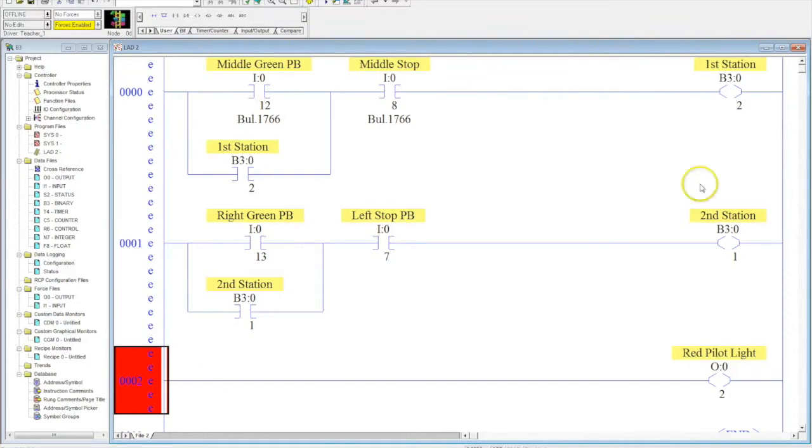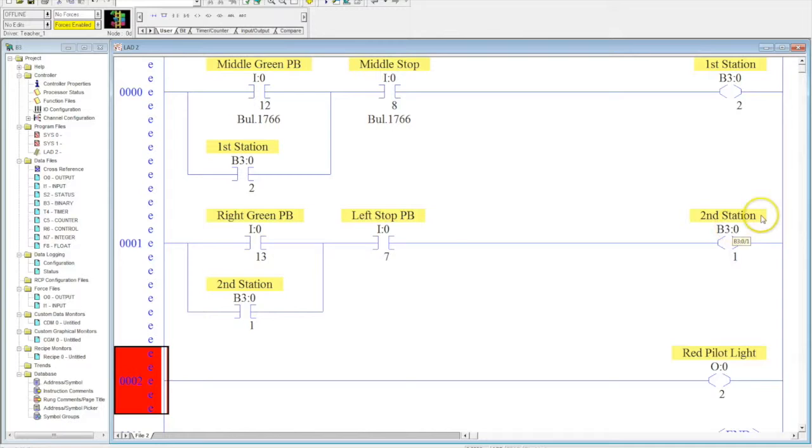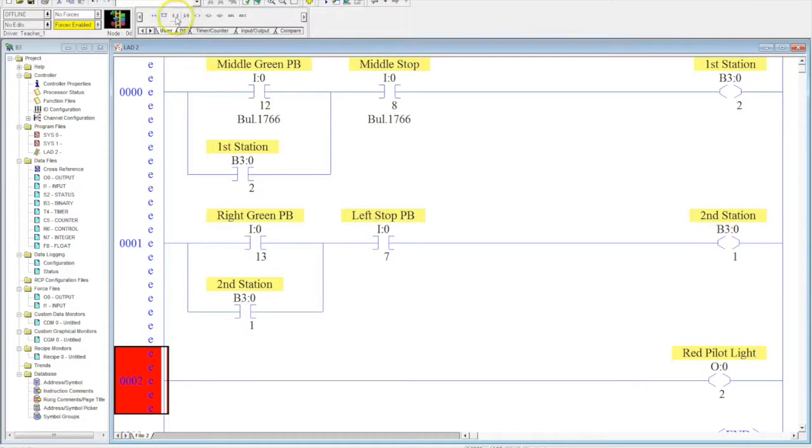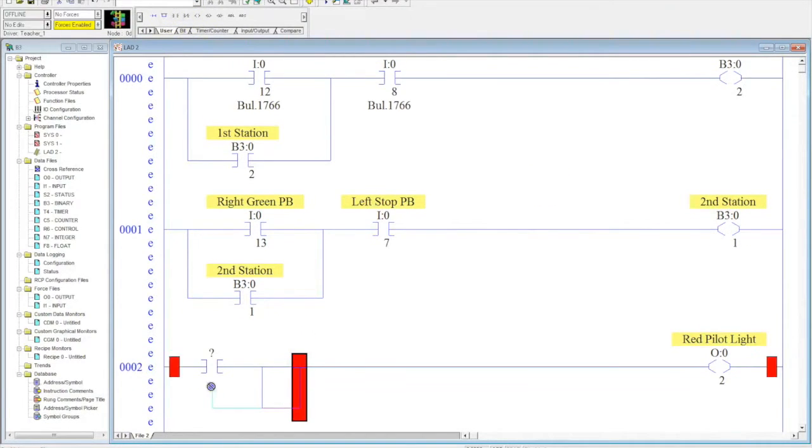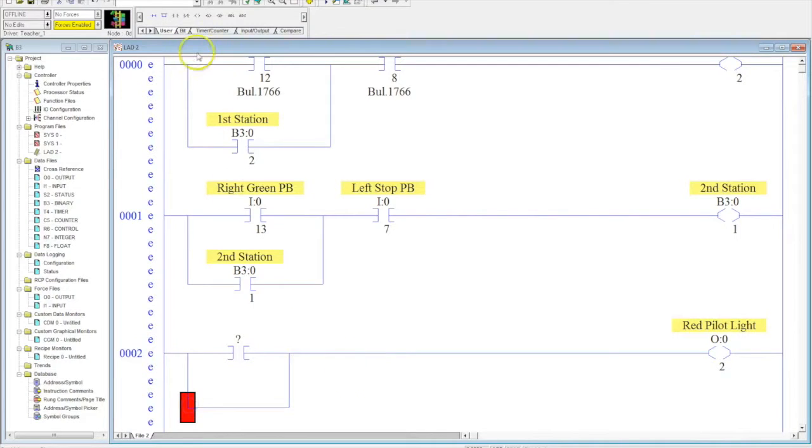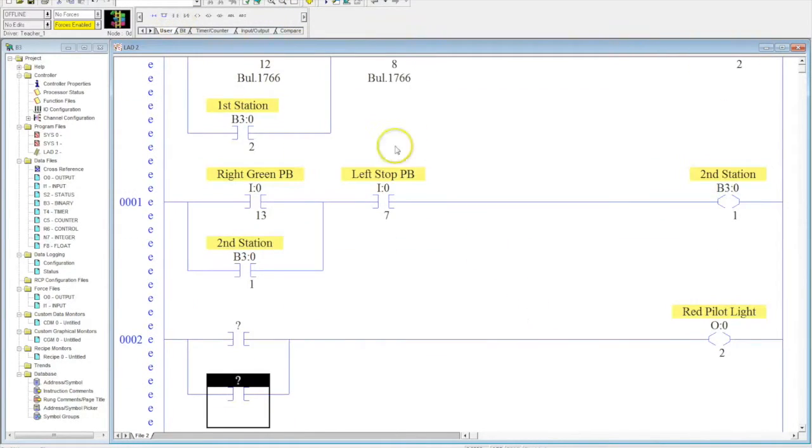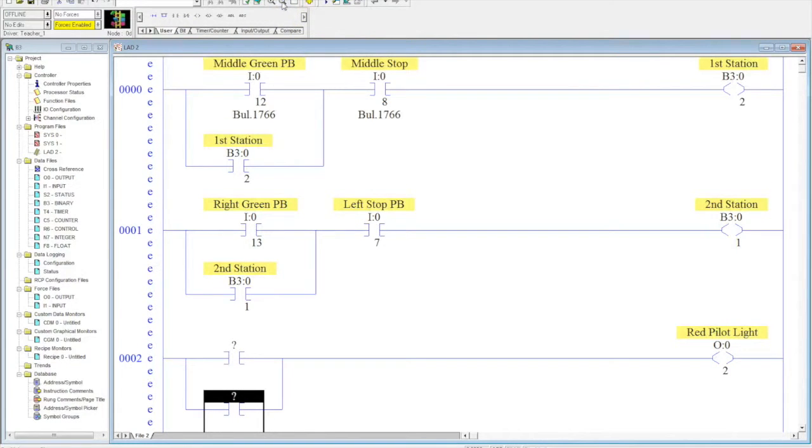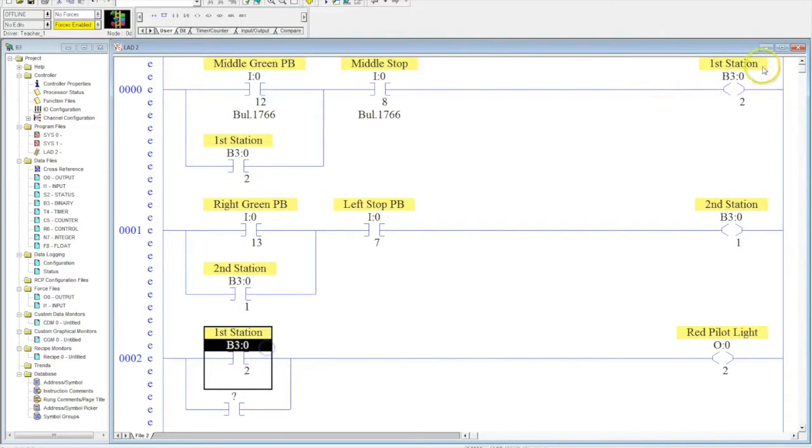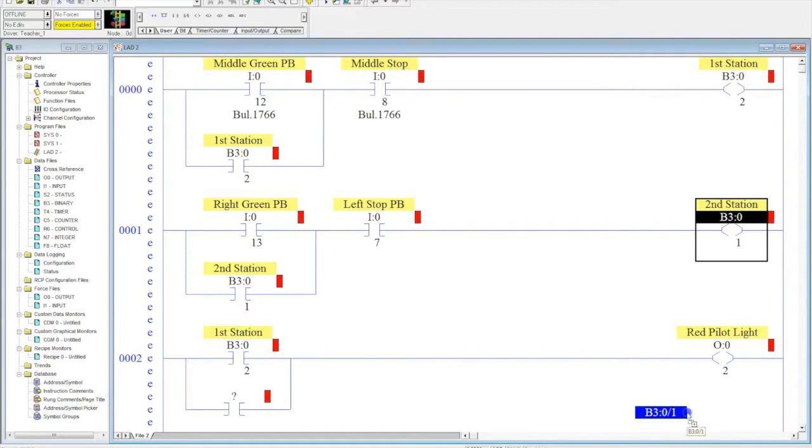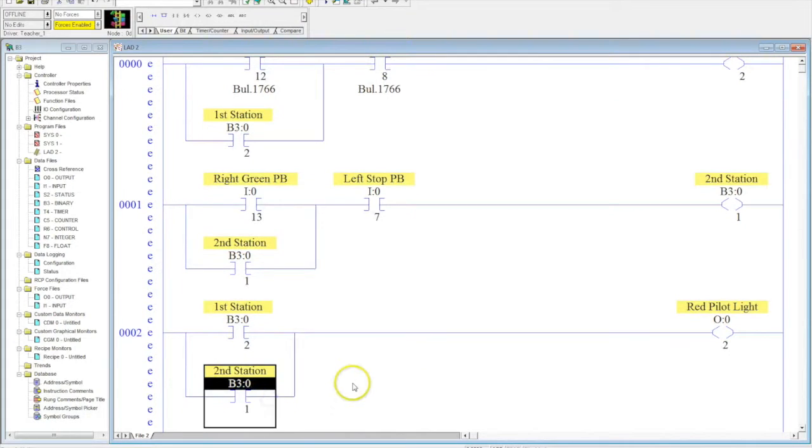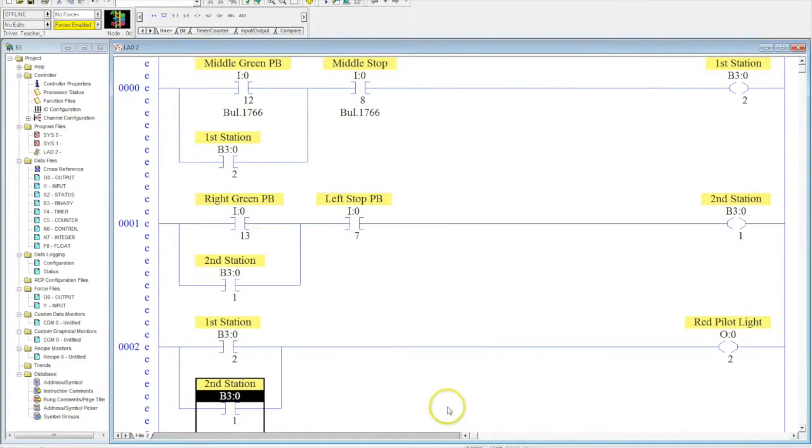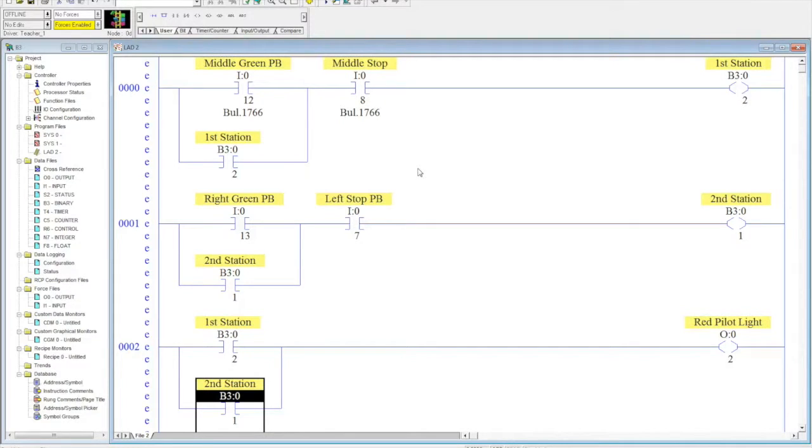Now what I have are two rungs. I have two start station rungs that are activating two different B3s. So basically what I'm saying is this light is going to be true if this one is on, or this light is going to be true if this one is on. And now that's an OR statement. So it's this or that. Anytime you have a pure OR statement, what you're going to do is just create a little parallel system here. I'm going to drop this down. Now you can see I can't see all this in one page, so I'm going to zoom out. I'm going to drag this one down to here, and this one down to here. What you're seeing is this is going to operate exactly like the last video that I showed you, with the exception it's going to be a lot easier to understand. And I can see exactly which station is being used.